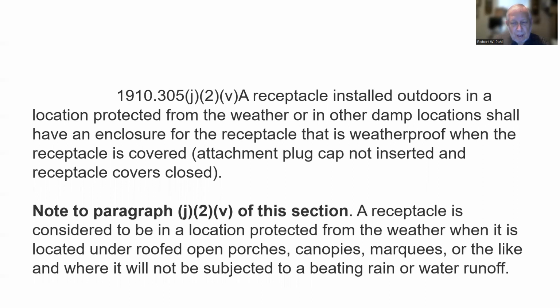A receptacle installed outdoors in a location protected from the weather or in other damp locations shall have an enclosure for the receptacle that is weatherproof when the receptacle is covered, attachment plug cap not inserted and receptacle covers closed. Note, a receptacle is considered to be in a location protected from the weather when it is located under roofed open porches, canopies, marquees, or the like, and where it will not be subjected to beating rain or water runoff.